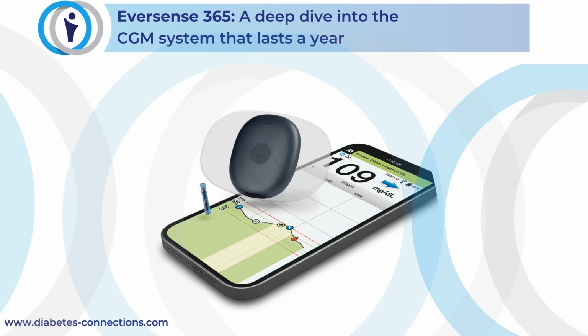So as you look at how it might communicate with a pump, today the sensor is powered and communicated, or the values are drawn out of the sensor that's underneath the skin by the transmitter. If the transmitter is not on the body, then as you just said, you're not getting a CGM value. So anytime that would happen, then depending on the pump's mechanism, it would fall back into its original settings and the patient would still be getting their basal rates based on however that pump is set. But it certainly wouldn't be in AID mode per se, because you would not be getting any value from the sensor when the transmitter is not attached to the silicone adhesive.